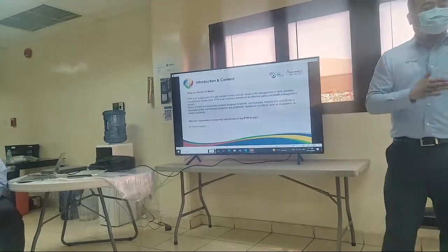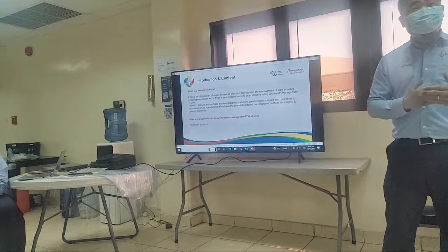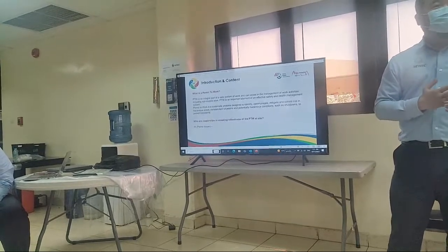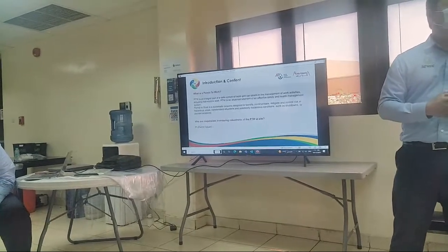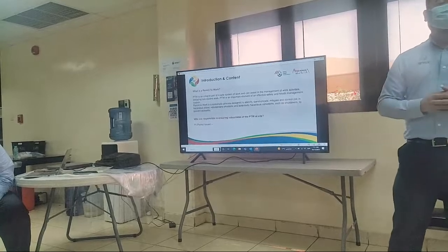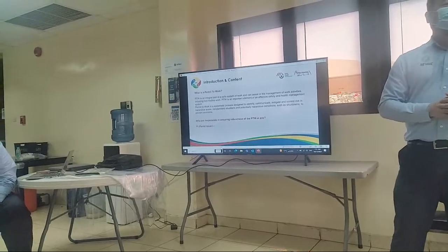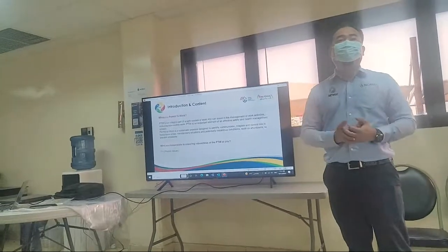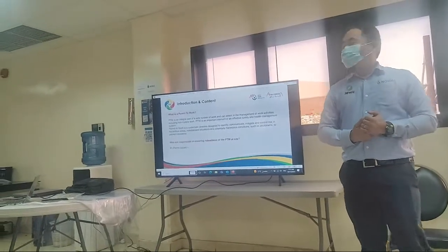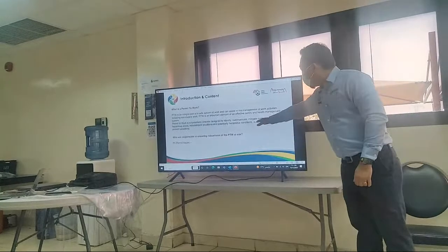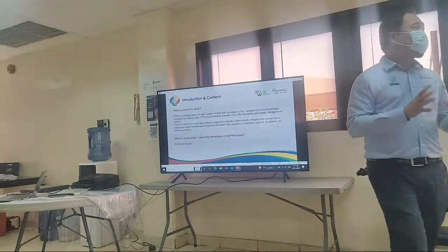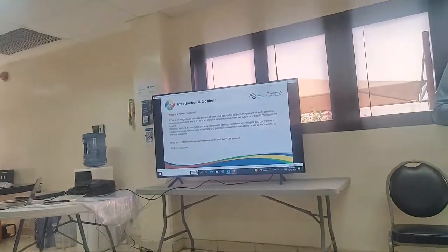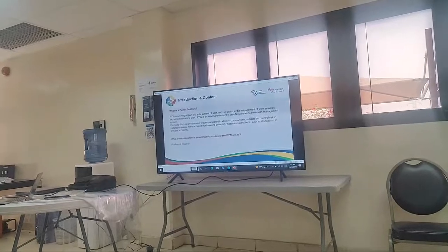Now, after the work has been completed, we have to communicate. The isolation authority, operation, will inform the next shift: this is the condition, these are the equipment being isolated, these are the equipment which are still active. Okay? Now, mitigate and control the risk. We have mentioned already in the JHA, we identify the risk, we identify the control measures.